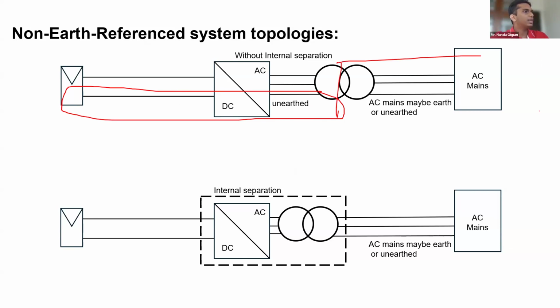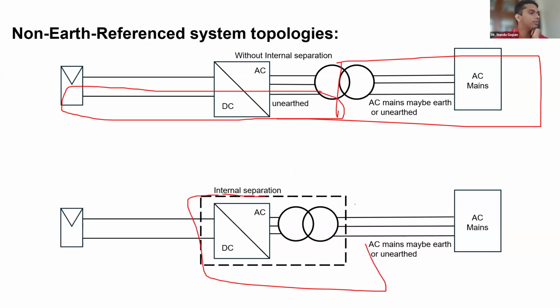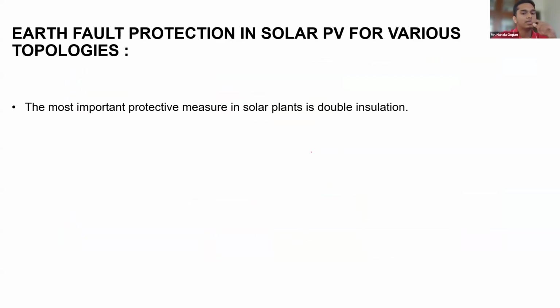And from the transformer, yes, it can be earthed or it can be unearthed. That depends. So it can also come without internal separation or with the internal separation. This will be in one PCE. So these are the three types of non-earth referenced system topologies. Now, I will be explaining how earth fault protection is done on each and every single system topology.